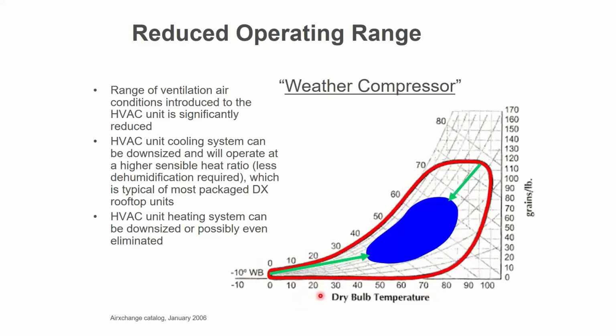This is a psych chart. Hopefully, you've all seen this before. Horizontally, 20, 40, 60, 80, 90 degrees of dry bulb temperature. Vertically is grains of moisture, so little droplets of moisture, if you will, 60, 80, 100 grains of moisture. A normal rooftop or air handler HVAC system is designed to do all of the work of the red bubble. Certain temperature day over here on the right, certain humidity on the top, certain low humidity on the bottom, certain low temperature on the left.